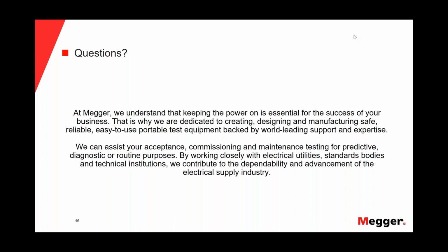It's not like you have a hesitation or you have to wait some time before it will happen. Typically, that's why you look at the inception voltage. When you bring the voltage up, you see what the inception voltage is, and then you look at what the extinction voltage is. But there should be no waiting time, and I'm not aware that there's any difference between AC, VLF, and DAC.